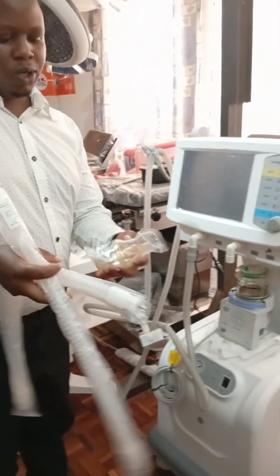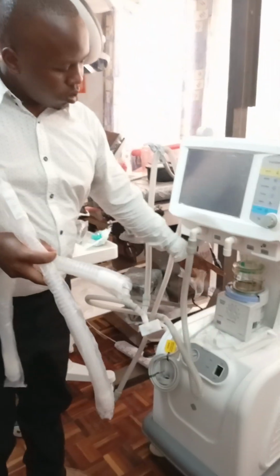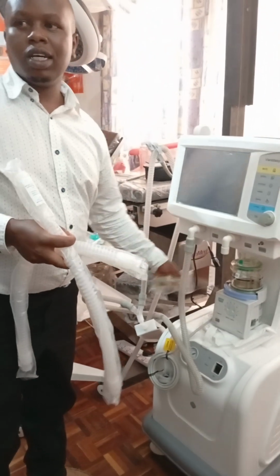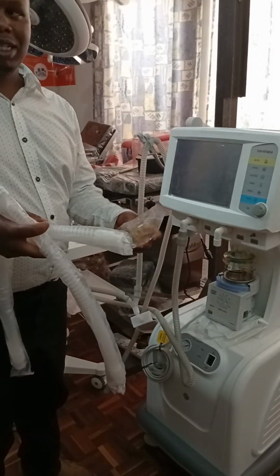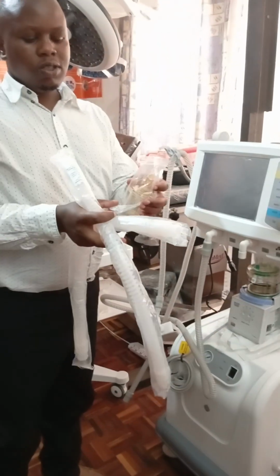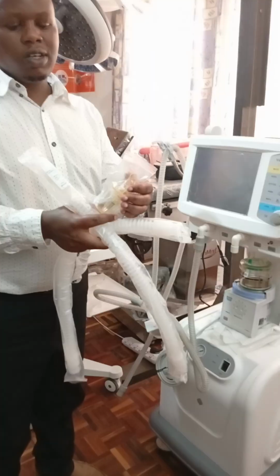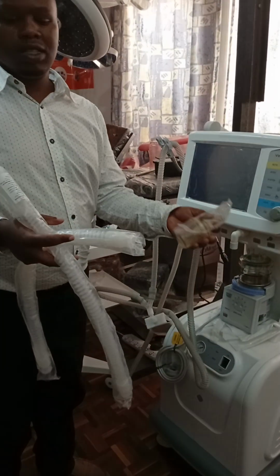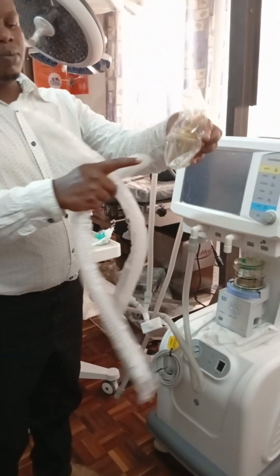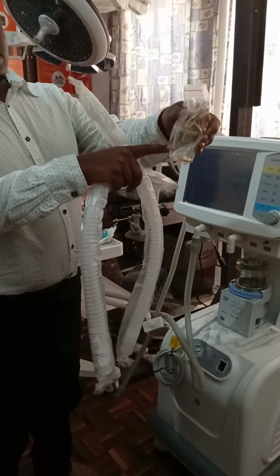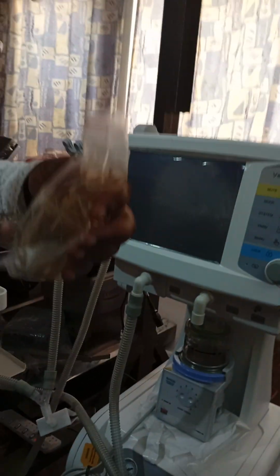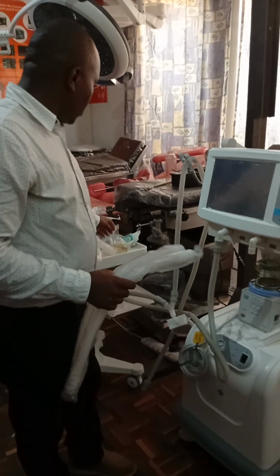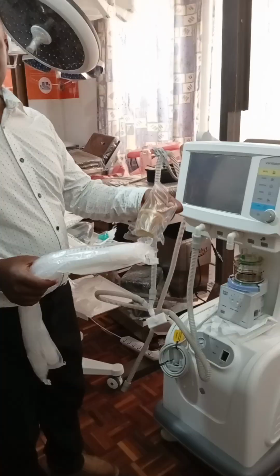This tube is called a water trap. In case the pressure coming through carries a lot of water, it will be trapped here. So you'll be checking regularly while the patient is using it. In case water gets filled up, mostly when it gets to this spring, you need to empty it. Do not allow it to fill, otherwise you can even kill the patient. From this water trap, now it goes to the patient.